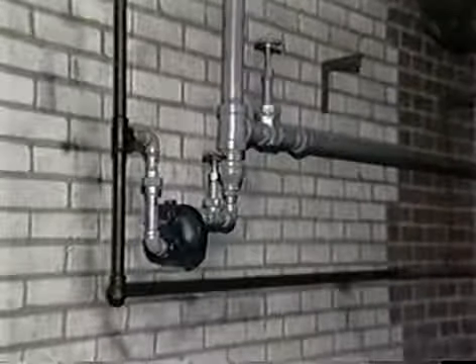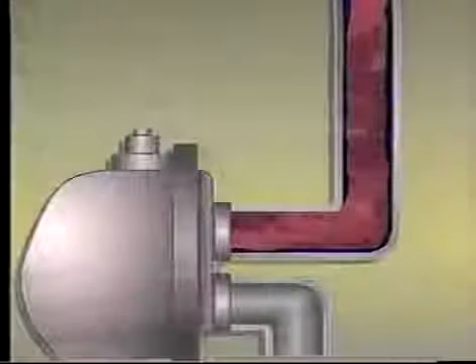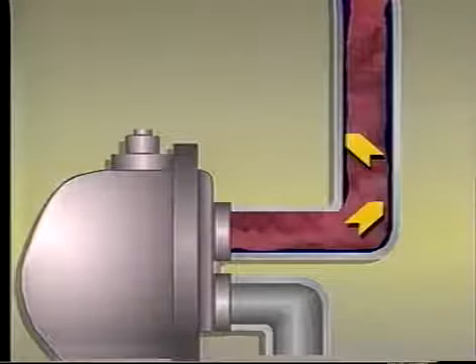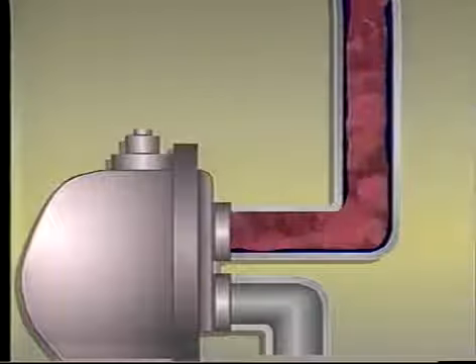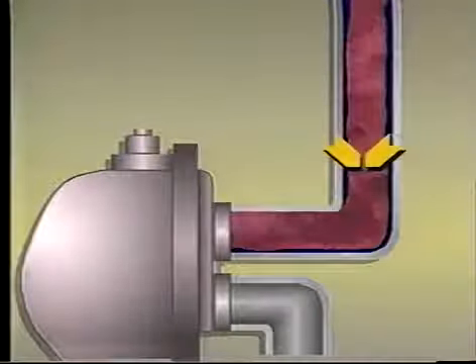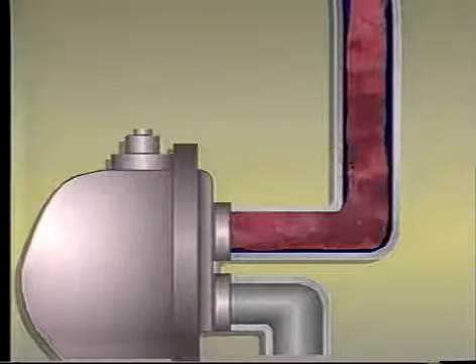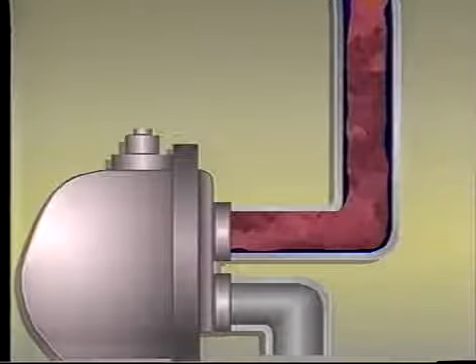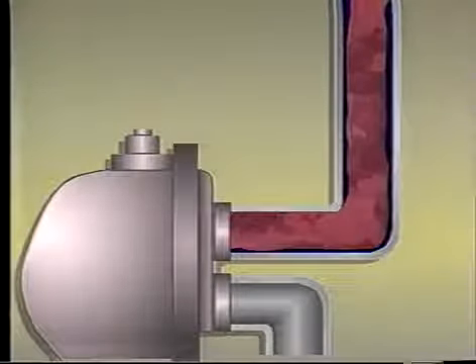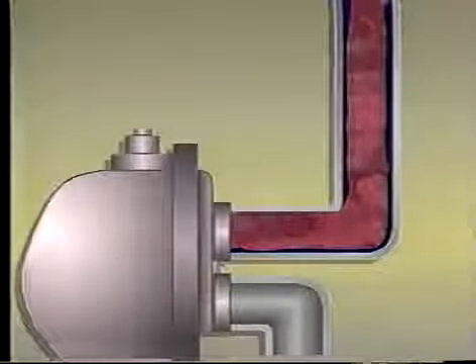Differential shock can also become a problem when elevated heat exchange equipment is drained with a substantial vertical drop ahead of the trap. Under normal conditions, condensate drains down the walls of the pipe. A sufficient volume of steam constantly flows down the center of the pipe to replace the steam that is condensed by radiation losses of the piping and the trap body itself. The steam flow rate increases if a thermostatic element such as the bellows or wafer in an F&T trap opens.